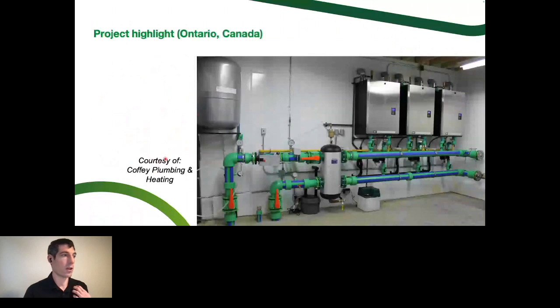And then we'll wrap up with just a couple pictures. This is one from Ontario. So this is with PPR. It could be copper, it could be PEX, could be anything, steel piping. Depends on the flow rate with this ECM circulator going out to the building, coming back to the hydro separator with the flange connections here. We're in good shape to keep these two loops separate. The ECM pump could be any number of GPM. We've got 3 different boilers that could come to life on this side, and they're not influencing each other.